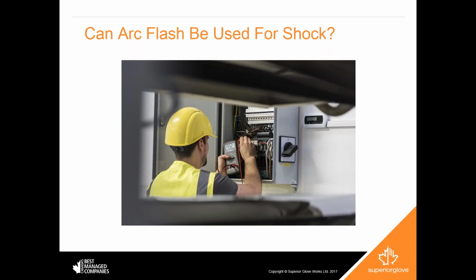From that, we go into our goatskin driver style gloves with Kevlar liners inside of them. Both are ANSI cut level A4 rated, and one carries an arc flash rating of 3. This is a standard goatskin glove with the Kevlar composite liner in it. And our Endura with oil block carries an arc flash rating of 4, which exceeds 40 cal. The advantage to this glove is that it is specially tanned so that oils and greases won't penetrate through the glove. And as we mentioned earlier, it's very important that once you use a piece of PPE around a piece of machinery, if you get it soiled, please launder it before you use it again. Otherwise, you could be leaving materials on your PPE that can increase your chances of a terrible accident happening.